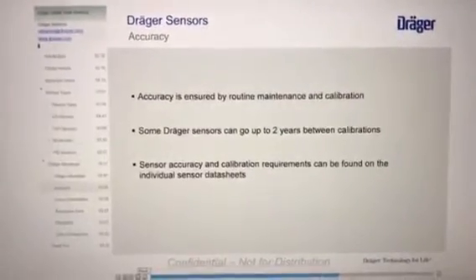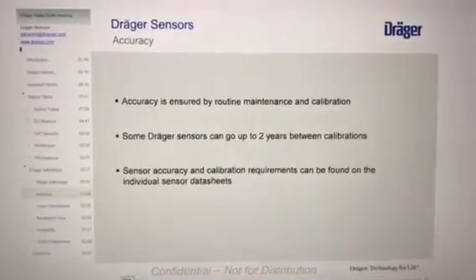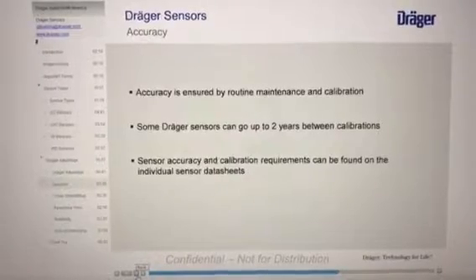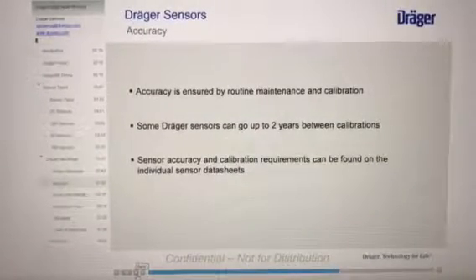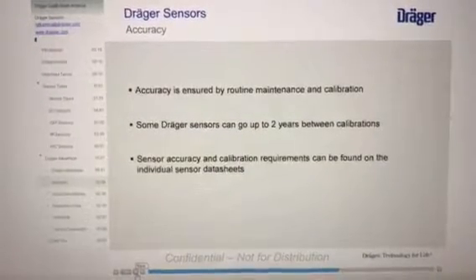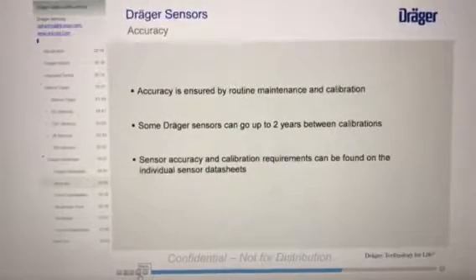It is important to perform regular maintenance and calibration on the sensor as suggested by the manufacturer. As an example, the Draeger carbon monoxide sensor found in the Pac instruments is only required to be calibrated every 2 years.